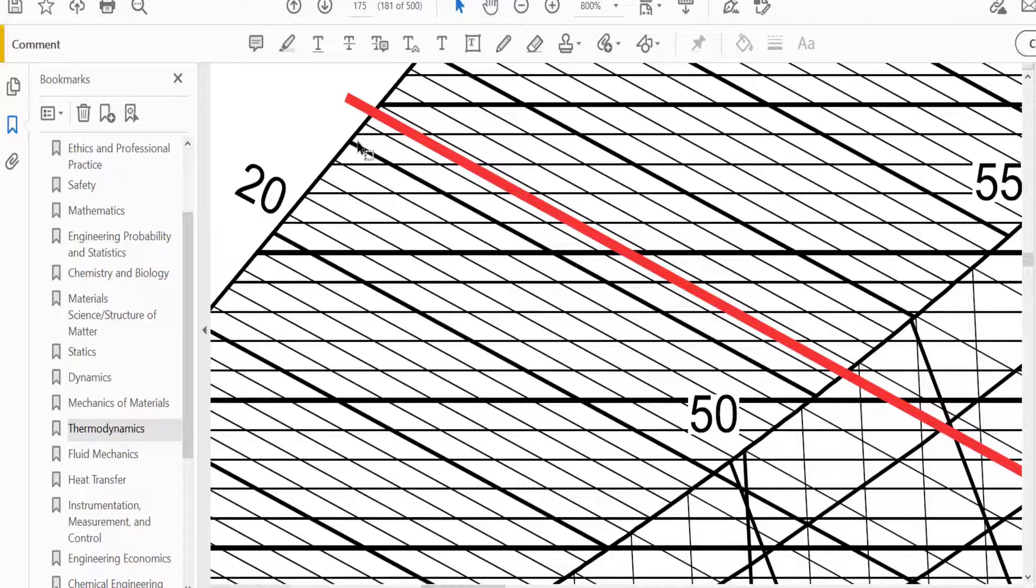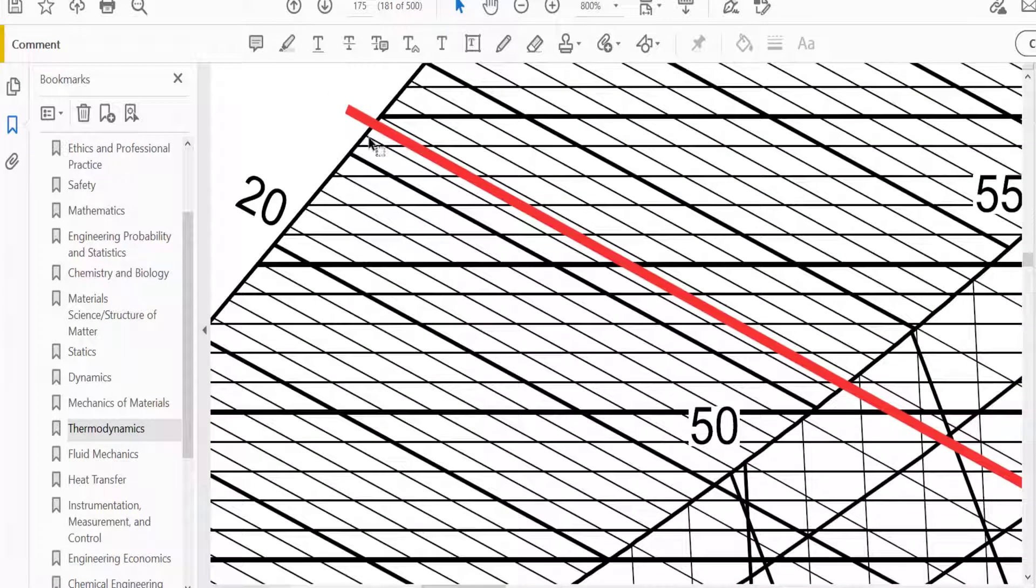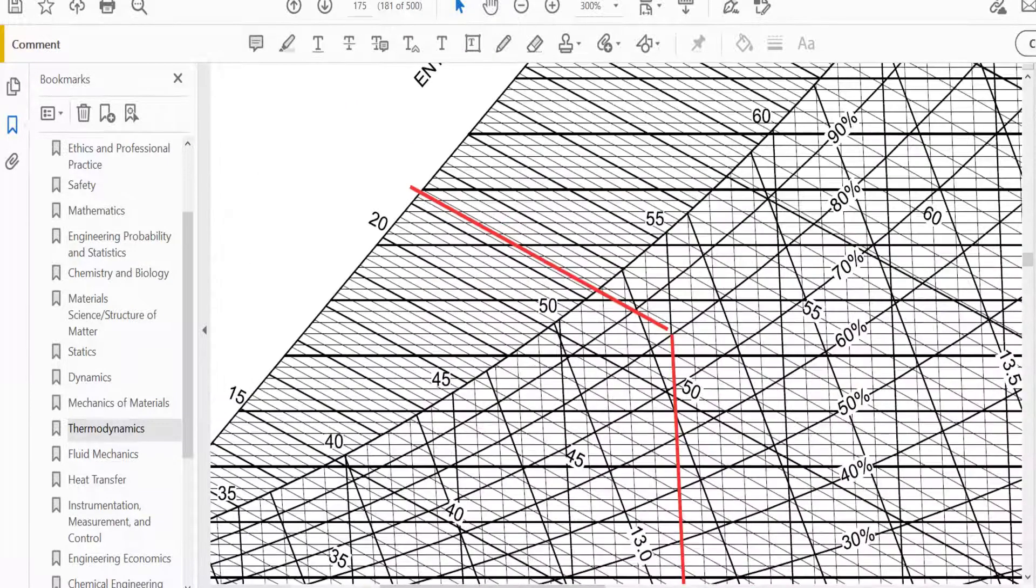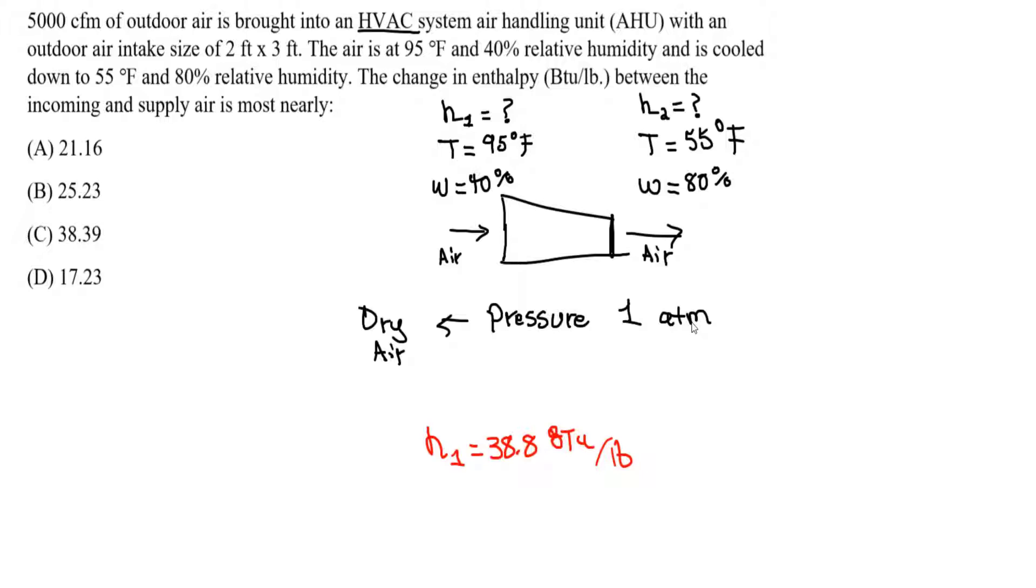So this is 20, this is 21, and this is going to be 21.2, this is 21.4, so we're in between these two. Counting the increments, this is 21.3, this point. So this is going to be our H2, 21.3, H2 equals 21.3 BTU per pound.